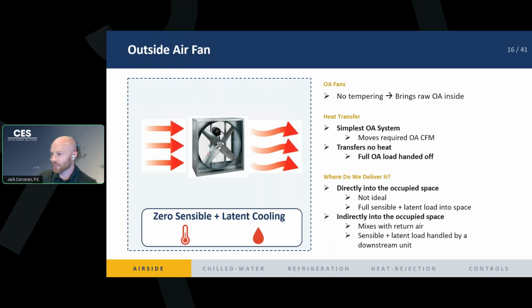It does have its advantages, right? If you're conditioning a warehouse, people aren't really in that space expecting to be at a very comfortable temperature. Of course, maybe we want to shoot for that, but in all reality, most warehouses are just dumping outside air into the space at the required minimum ventilation. And they're comfortable with the air getting up to 95 degrees. That space can get hot in the hot days of the summer, but they are fine with that because most of the year, maybe the outside air isn't as hot or as cold, and they can get away with not tempering it. So it's a simple solution.